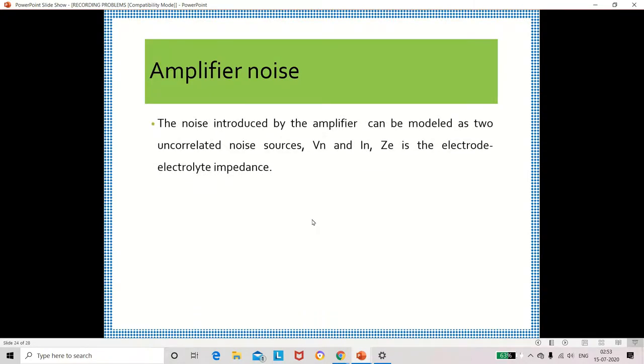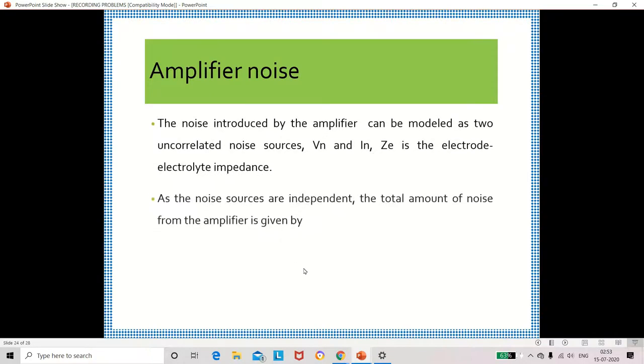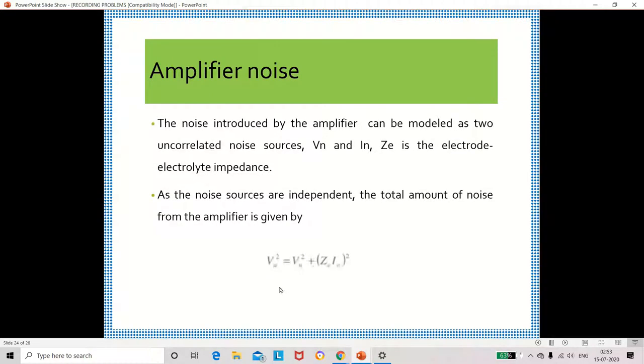The total amplifier noise formula is: VA² = Vn² + (In × Ze)², where VA is the amplifier noise voltage, Vn is the noise due to voltage, In is the noise due to current, and Ze is the electrode impedance.